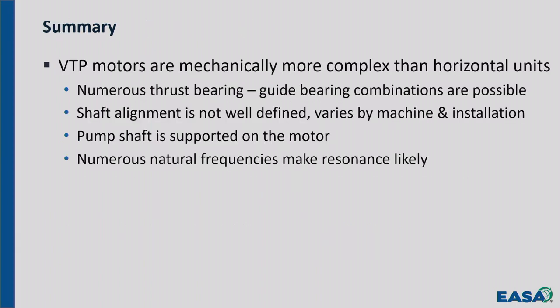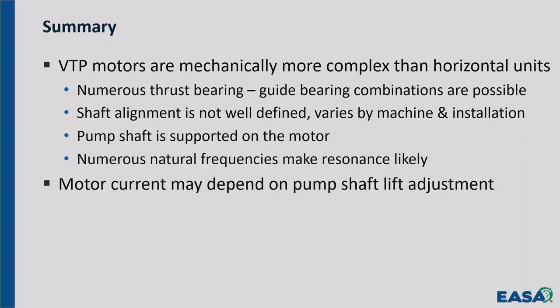So mechanically, vertical motors are more complex, particularly in that bearing in the top, with all the different types of bearings that can be in there. Alignment is a problem. They're just not designed for alignment. Those motors are made to be set on top of a perfectly true motor flange, and you don't have that. They're not made to be adjusted. So that's a problem that needs to be dealt with. You can't turn the pump shaft unless it's already hooked up to the motor. And you have the problem with natural frequency and resonance, which is always going to be there. And in some cases, with an open-style or semi-open impeller, the motor current depends on the amount of clearance at the bottom.